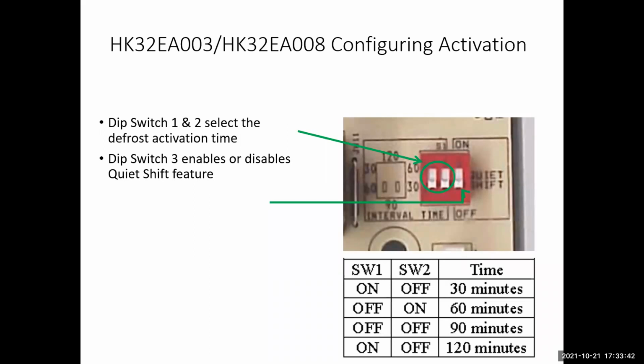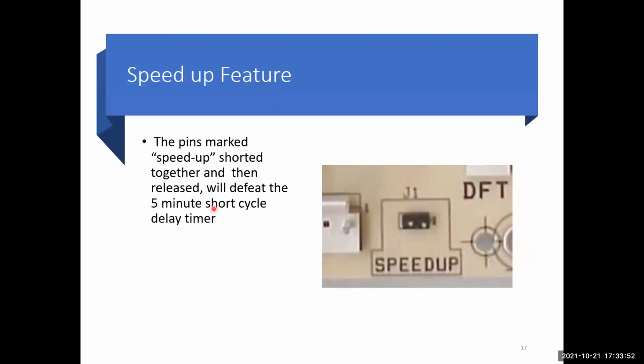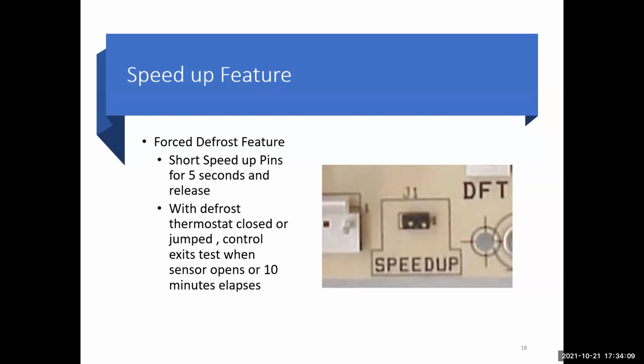Definitely a good feature and really helps with compressor noise level in and out of defrost. Excuse me. The pins marked speed up, short together, then released, will defeat the 5-minute short cycle time. So that's going to be a quick little bump between these two speed up terminals. Same speed up terminals again, we're going to bump it, but hold for 5 seconds. The defrost thermostat's going to close, or jumper. After 5 seconds, you click it off, and that's going to override that time.